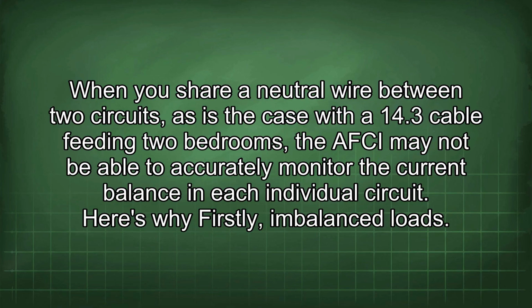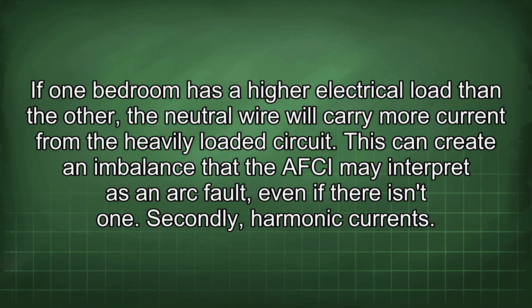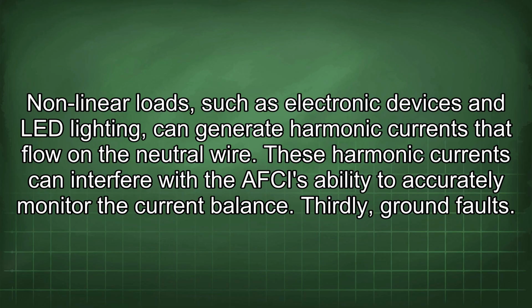Here's why. Firstly, imbalanced loads. If one bedroom has a higher electrical load than the other, the neutral wire will carry more current from the heavily loaded circuit. This can create an imbalance that the AFCI may interpret as an arc fault, even if there isn't one. Secondly, harmonic currents. Nonlinear loads, such as electronic devices and LED lighting, can generate harmonic currents that flow on the neutral wire. These harmonic currents can interfere with the AFCI's ability to accurately monitor the current balance.